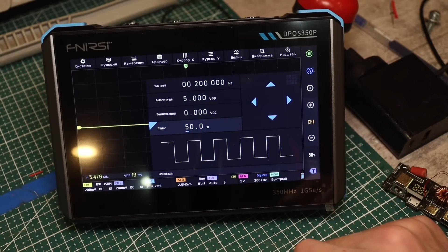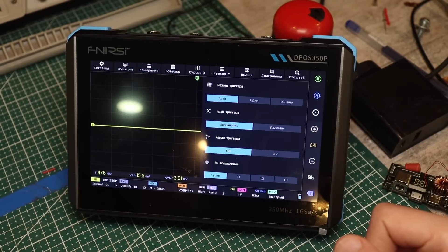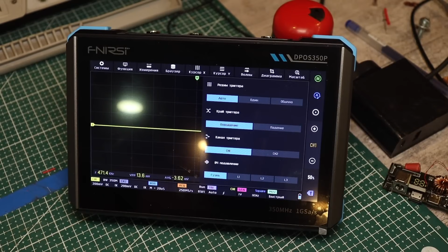I skipped over the trigger settings, they're standard here. You can select the trigger channel and you can also choose the operating mode. That's single mode, normal mode, or auto mode, and you can trigger on the rising or falling edge. A lot of people are specifically interested in capture. For example, how well the oscilloscope can capture fast single pulses. This is actually important. We use this feature often, and of course we'll be testing all of it.